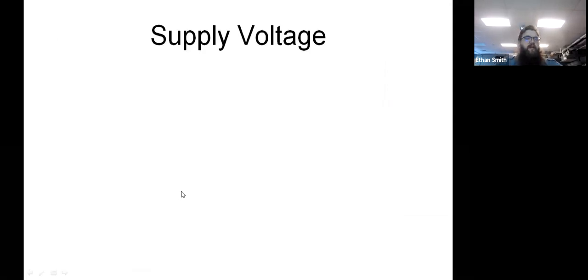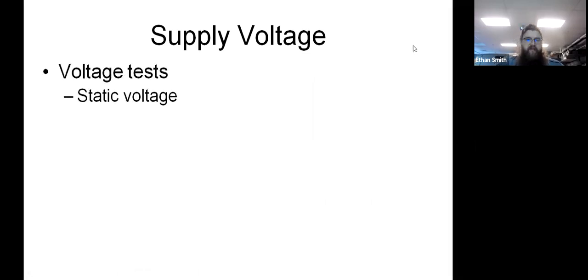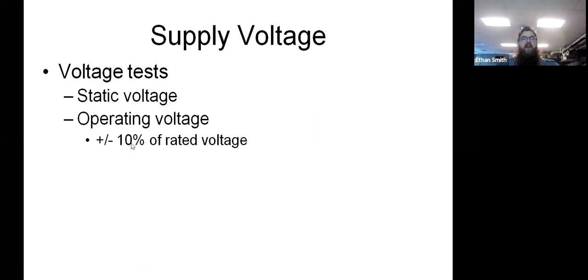So let's talk a little bit about supply voltage checks, guys. We didn't talk about this in Keith's class, I don't think. There's a couple voltage tests you need to do on everything you touch, especially if it's having troubles. You want a static voltage test. This is a voltage when the unit is at rest. You want an operating voltage test. And that operating voltage test needs to be within plus or minus 10% of your rated voltage.